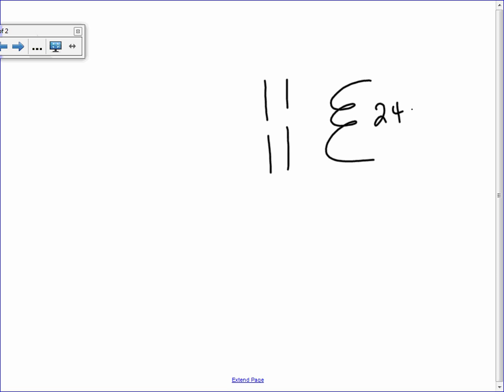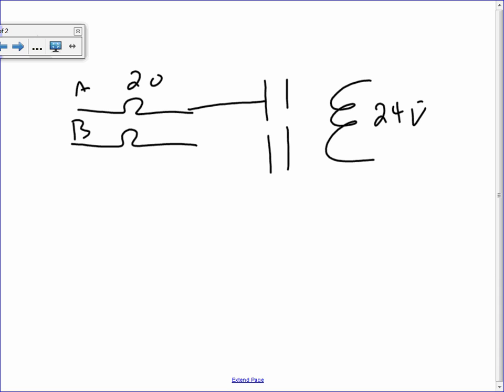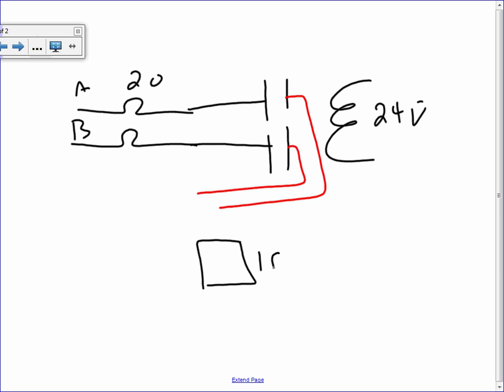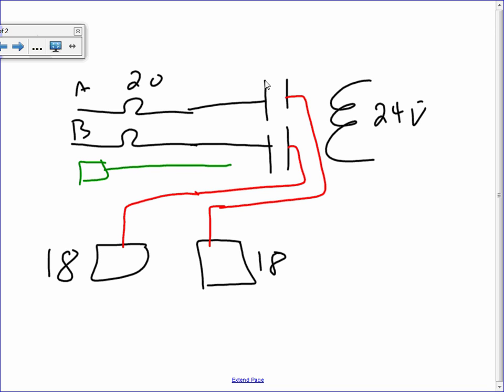Here's my 24 volt here, and I can have two poles, meaning I can bring two circuits. Here's circuit 1, 20 amp, phase A, circuit 2, phase B. I bring this circuit to this one, and this circuit to this one, come out as two poles, and go to my lighting fixtures, grabbing my fixture. Here's 18 fixtures here, and another 18 fixtures here. I grab my light, bring it down here and here, and of course don't forget the neutral.